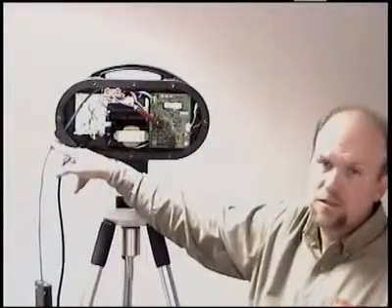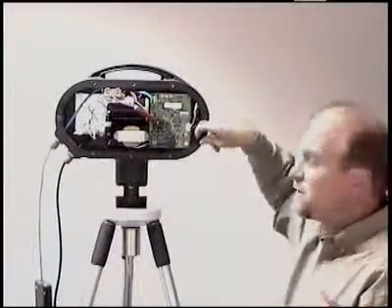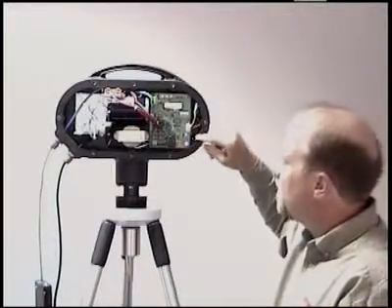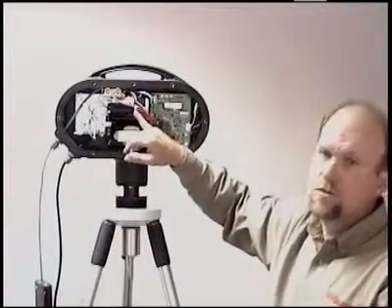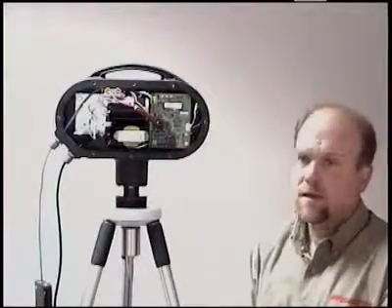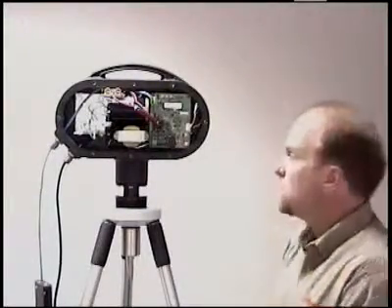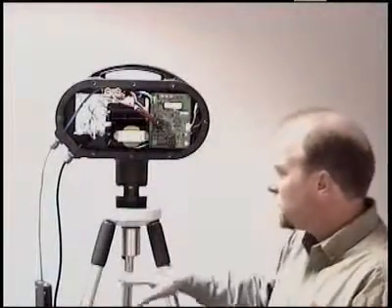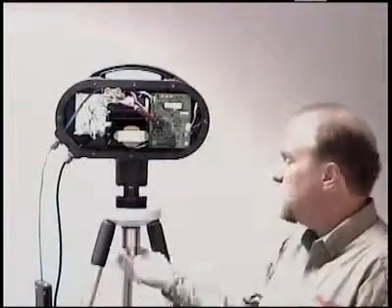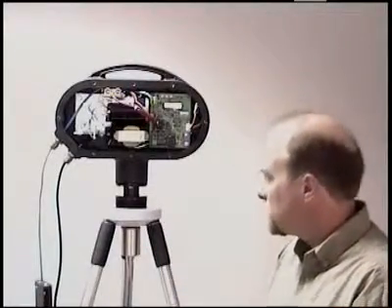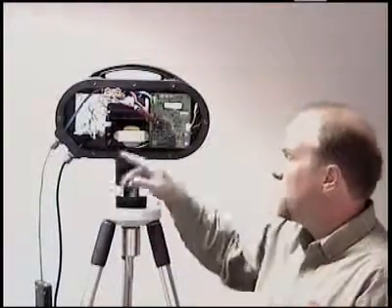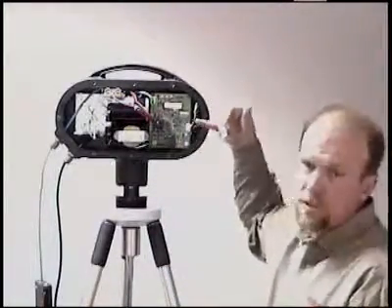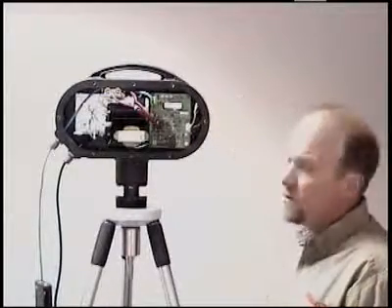We have dual conduit entries, a water and dust tight sealed electronic cavity. We've also gone to a direct drive heavy duty reversible motor with electronic torque control to assure that we get full maximum power throughout the measurement cycle. We control the torque at the top 12 inches of the retract cycle to protect the gears and components within the PC board.